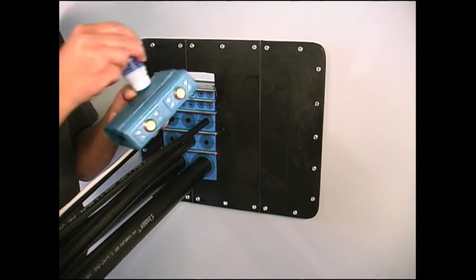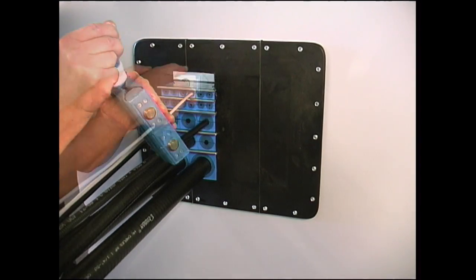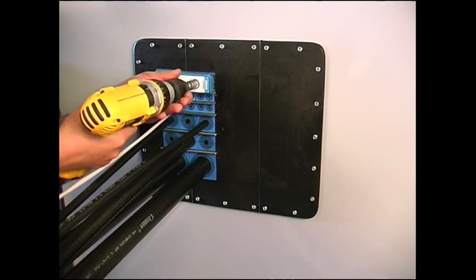Lubricate the Roxtec wedge and insert it into the frame. Tighten the bolts alternately until stop or to a maximum torque of 20 Nm.